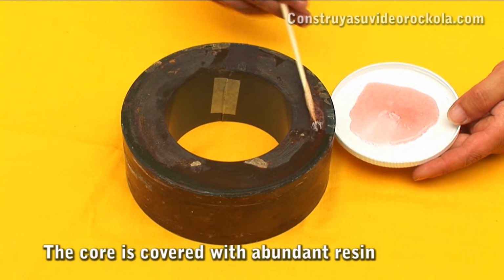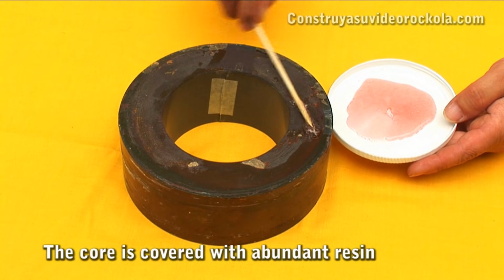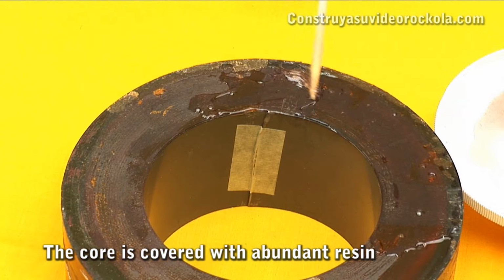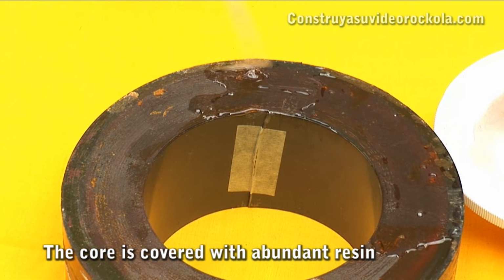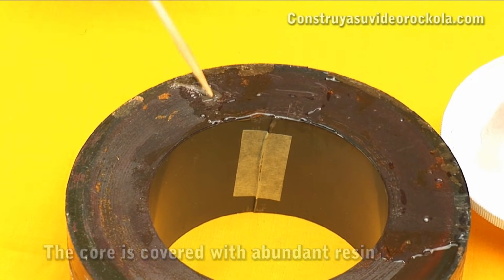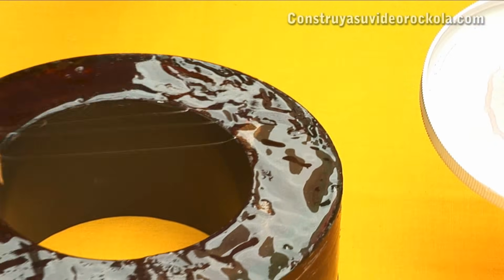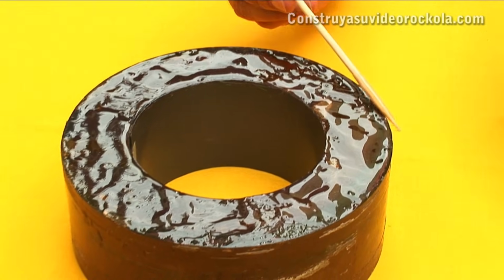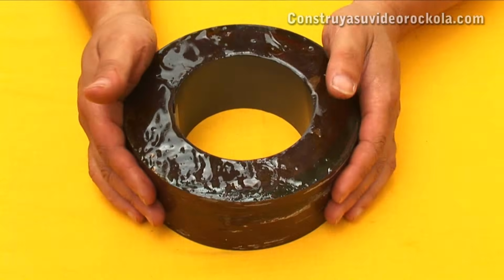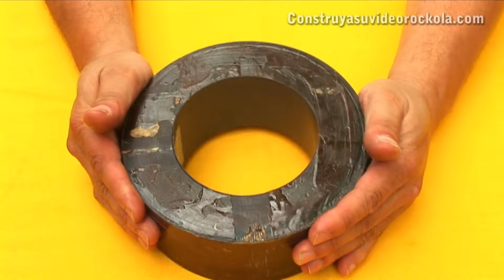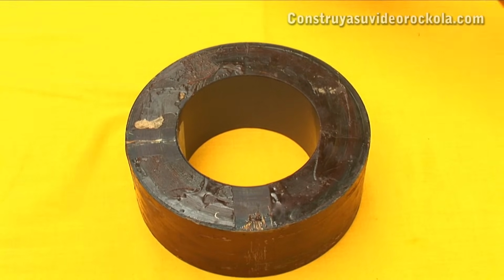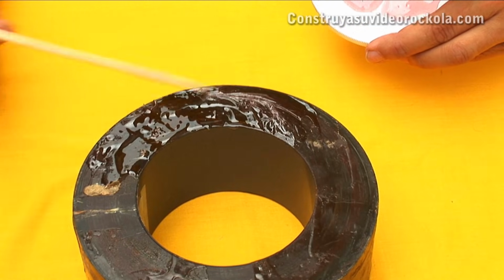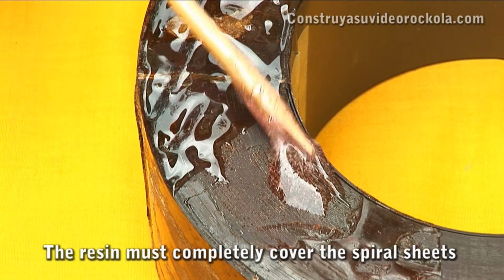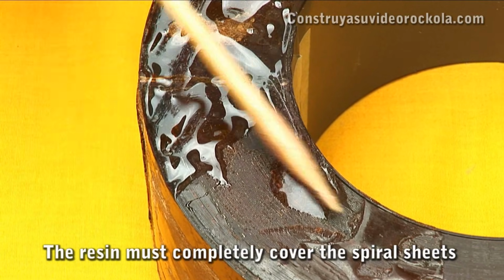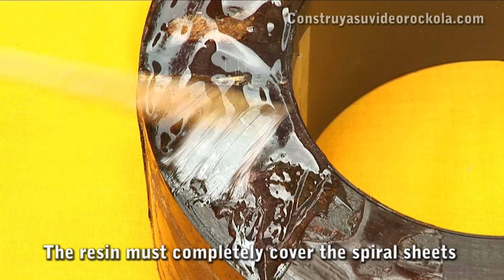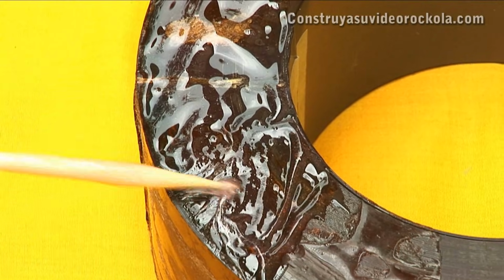Then apply the resin liberally to the spiral of the core, bonding the turns of the plating. When the resin is completely dry, the core is flipped and the resin is applied on the other side. This process is done to prevent the plates which form the core from rubbing against each other because of the vibration generated, which ultimately becomes heat.